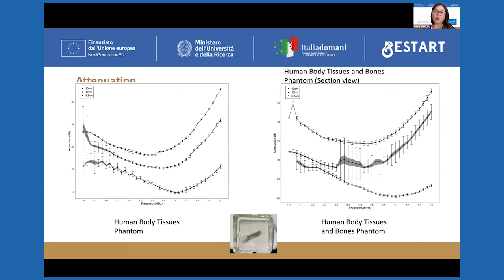In this slide, we also reported some experimental data that we obtained by characterizing the attenuation as a function of the frequency for a human body phantom, that is this one reported here, that is a block of ballistic gel that exhibits the same features of the human body tissues, embedded with organic tissues like chicken bone. And these are the two situations. This case when the phantom was without the organic tissues, and this case when there was this organic tissue. Please note that the attenuation depends, as we said, on the size of the block.